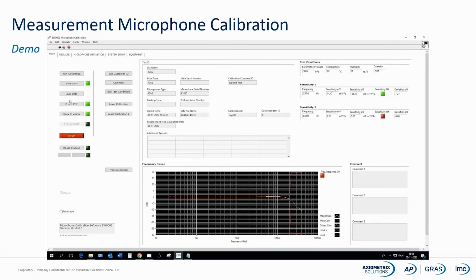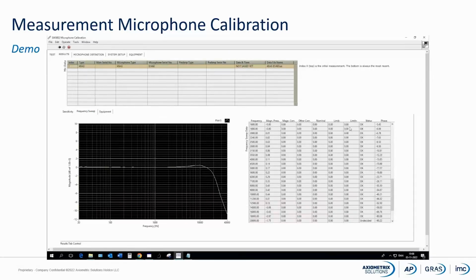It was actually the calibration, but let's have a little look at the results. So we have the results here where we have the microphone. That's one measurement. Here, if I press this one here, then I can actually see the frequency response of our measurements. I also have, if I press the sensitivity, the possibility to see how the sensitivity is. If we have made many calibrations of these microphones, then I will actually be able to see all the different calibrations, and I could actually compare these and see if the microphone has drifted over time.